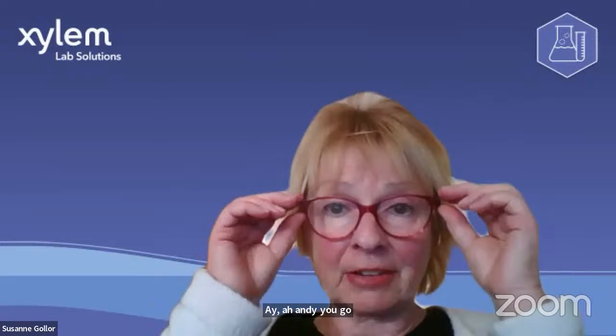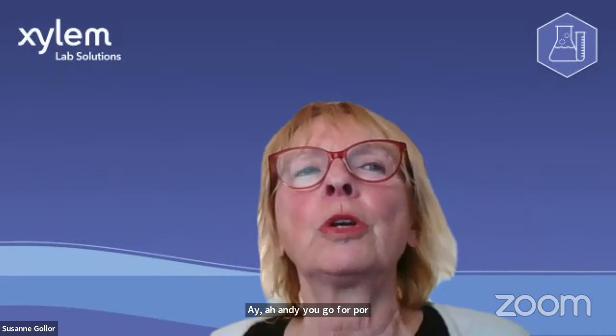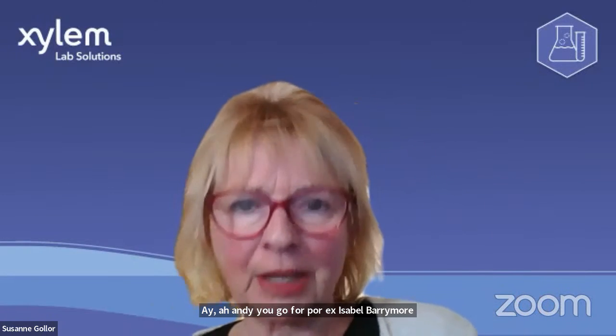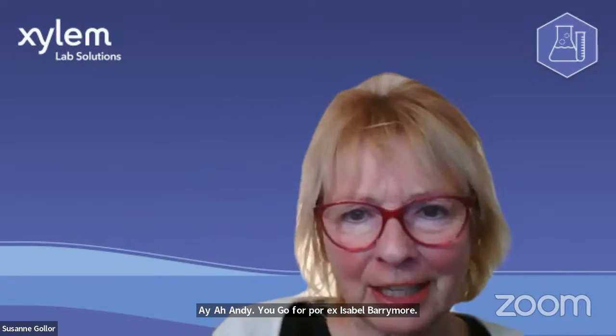And if you go, for example, for very small particles, you would take a white light because of the wavelengths of the white light in the range of visible light and the 400 to 600 nanometer detector. So small particles. And then sometimes, if you have samples which you are not sure about, it could be eventually useful to test with the two different light sources.